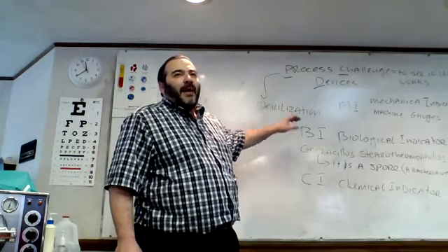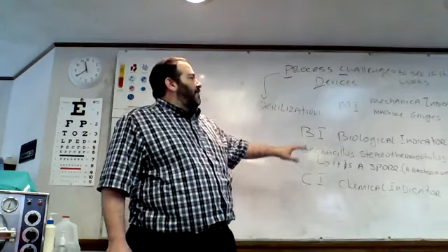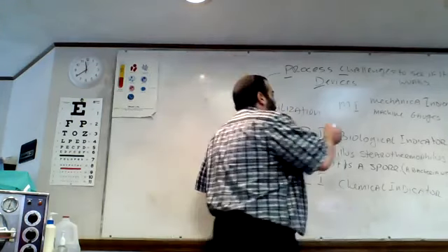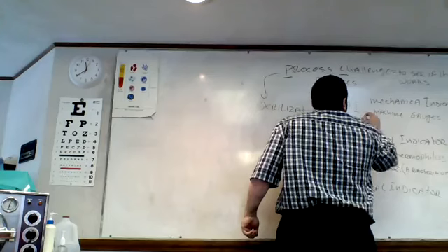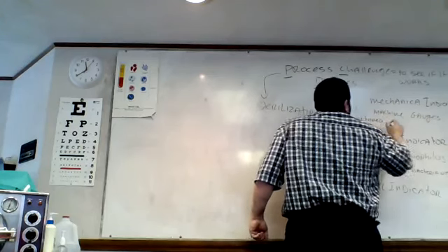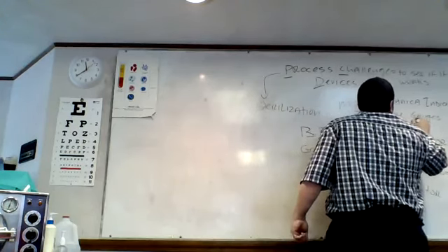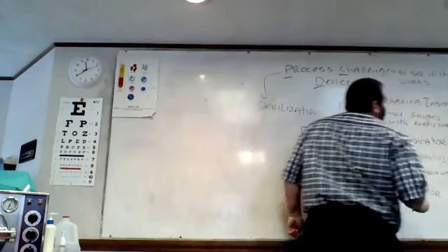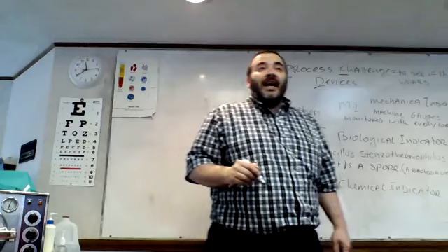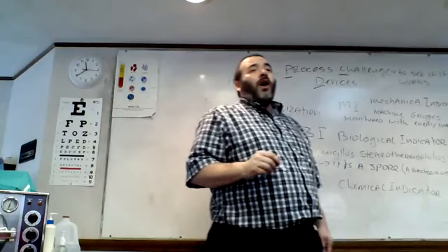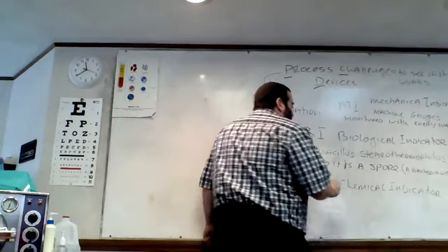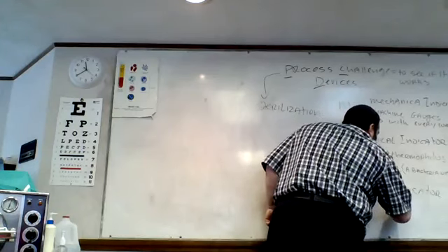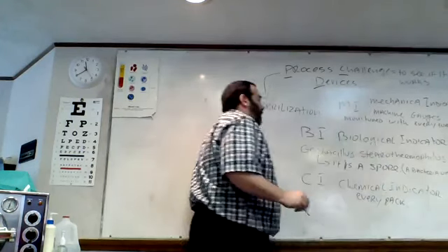Mechanical, biological, chemical. Now, mechanical indicators are monitored with every load. Meaning, every time you load up your sterilizer, you better make sure that you watch your mechanical indicators. Chemical indicators: every pack contains chemical indicators.